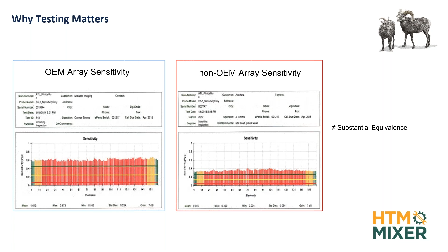We talked about taking things off of the probe. This is what the sonographer was complaining about. You see all the noise bars in there and everything else like that, rolling noise bars in real time. It's pretty spectacular. Never did that before, and so we got it in. We popped it open to take a look. Whoever went in there took out the EMI shielding material and also adulterated the grounds on the side here. So it was picking up any noise in the hospital. Anybody ever seen a Bovie next to an ultrasound machine? Oh my word, it's pretty interesting. Or a microwave oven for that matter in the room next to it. You lose your EMI shielding, that's what you're going to get.